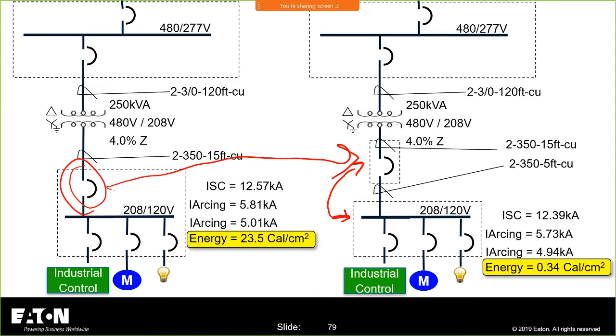And now all you've done, right? I've taken this 23.5. I had somebody tell me this. I went through this and they were like, wow, all you did was move the energy up there. You didn't get rid of the energy. That is true. I moved the 23.5 calories from the panel board up to this enclosure. Now, what I would ask you is, which will you get in more often? Will you get into this breaker in a box or fusible switch, or will you get into that panel board more often? I think the answer is you will get into that panel board heck of a lot more often than you will into that single enclosure with an overcurrent device.